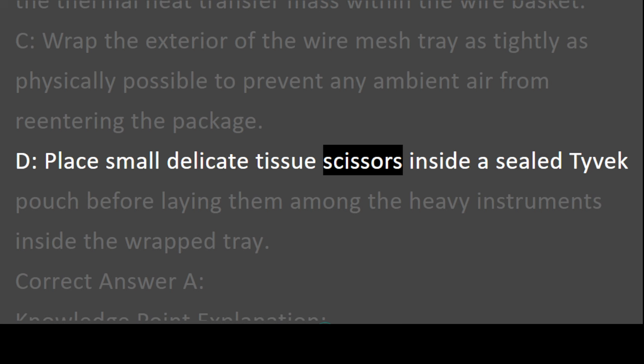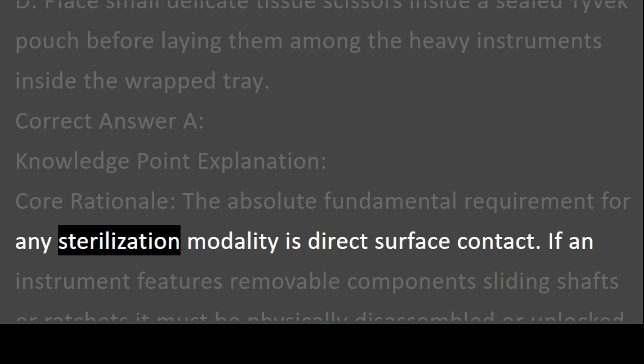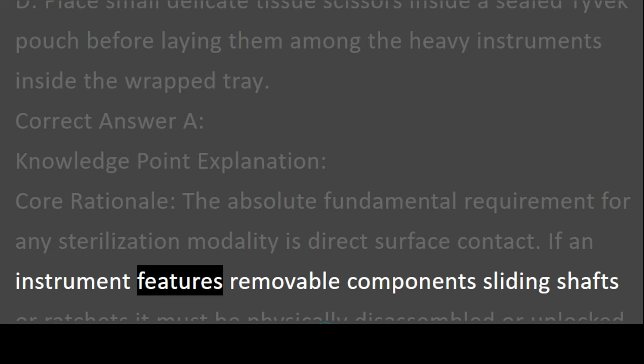Correct answer A. Knowledge point explanation. Core rationale: The absolute fundamental requirement for any sterilization modality is direct surface contact. If an instrument features removable components, sliding shafts, or ratchets, it must be physically disassembled or unlocked so the sterilant vapor can freely reach and eradicate microbes on the interior friction points. Trap analysis. Option B. High density creates a massive metal heatsink that blocks steam penetration and guarantees wet packs.